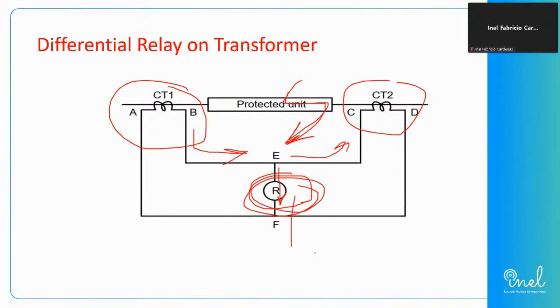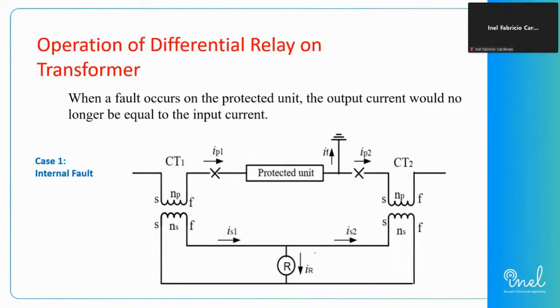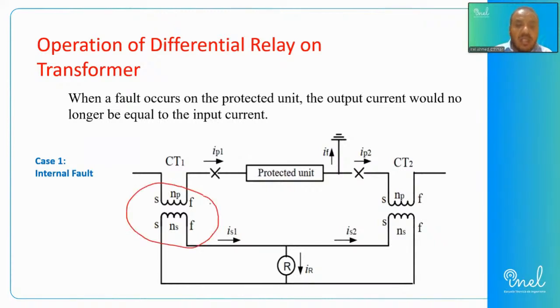So let us proceed at least to confirm how our differential relay on a transformer will operate. Again, it's the same concept. We have a transformer. We are using a current transformer at the primary side to sense the current at side 1, and we have a current transformer at the secondary side to sense the current on the other side.